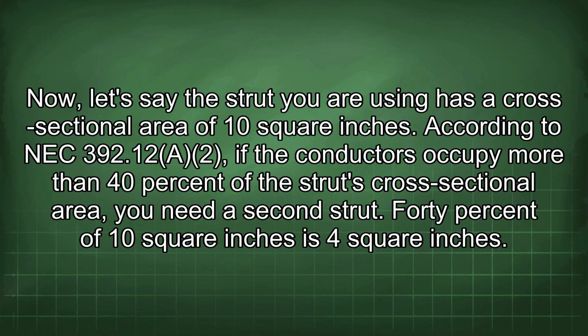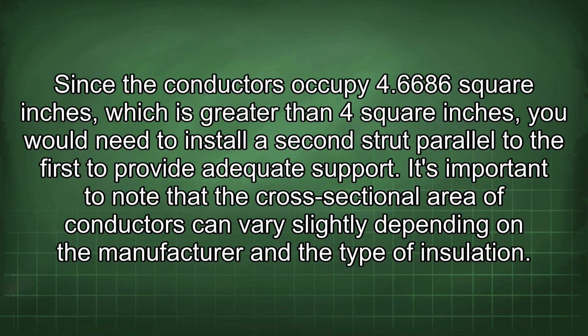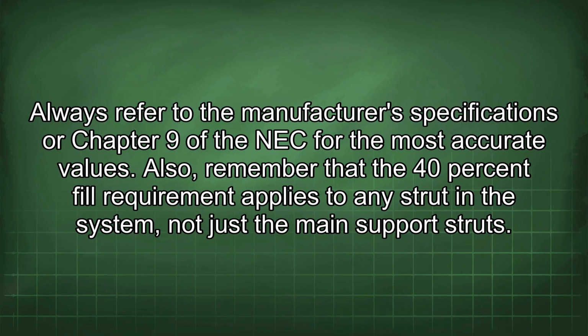According to NEC 392.12, if the conductors occupy more than 40% of the strut's cross-sectional area, you need a second strut. 40% of 10 square inches is 4 square inches. Since the conductors occupy 4.6686 square inches, which is greater than 4 square inches, you would need to install a second strut parallel to the first to provide adequate support. It's important to note that the cross-sectional area of conductors can vary slightly depending on the manufacturer and the type of insulation. Always refer to the manufacturer's specifications or Chapter 9 of the NEC for the most accurate values.